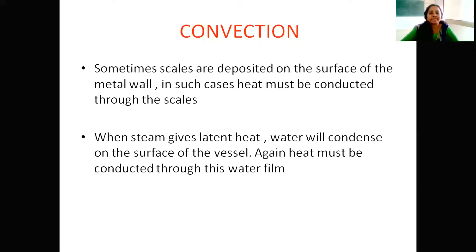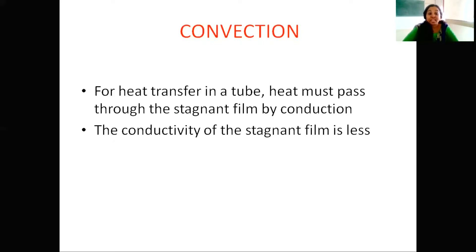In such cases, heat must be conducted through the scales. When steam gives latent heat, water will condense on the surface of the vessel. Again, heat must be conducted through this water film. For heat transfer in a tube, heat must pass through the stagnant film by conduction. The conductivity of the stagnant film is very less.